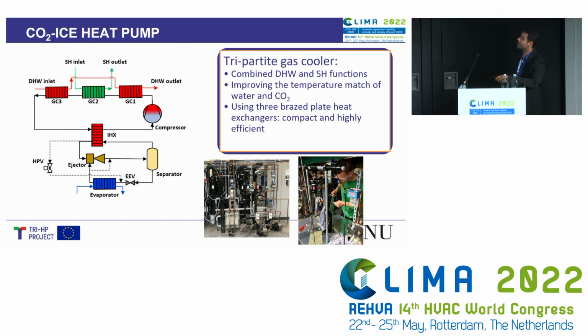But how does the system work? The high temperature, high pressure refrigerant gets out of the compressor and passes through the tripartite gas cooler, then comes inside the internal heat exchanger, ejector, evaporator, and separator, and then goes to the suction of the compressor.